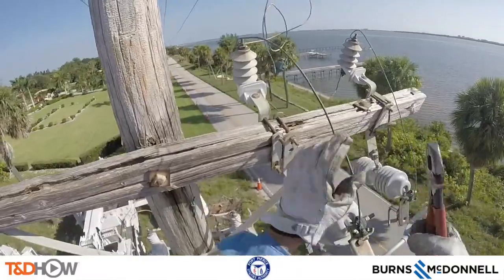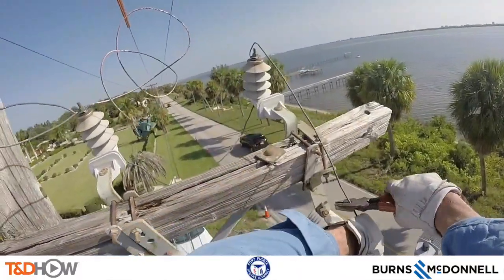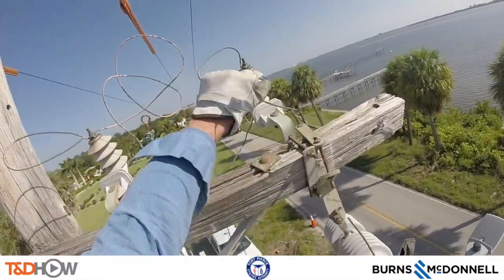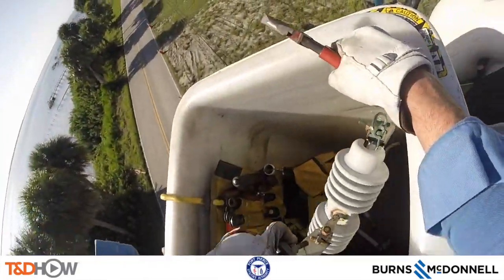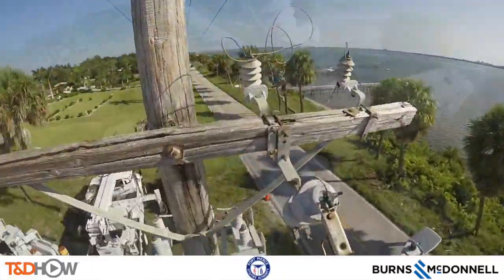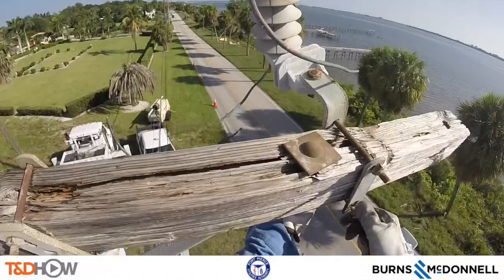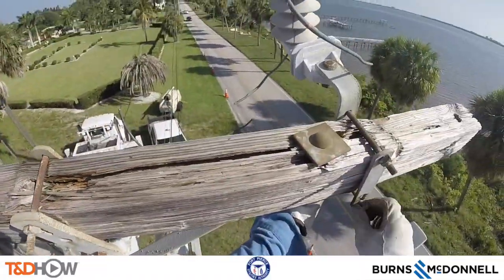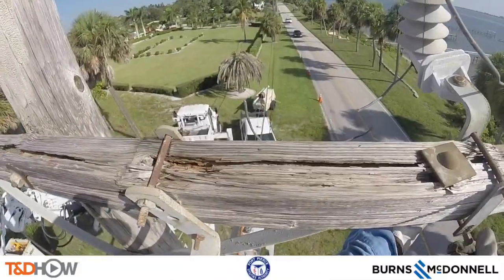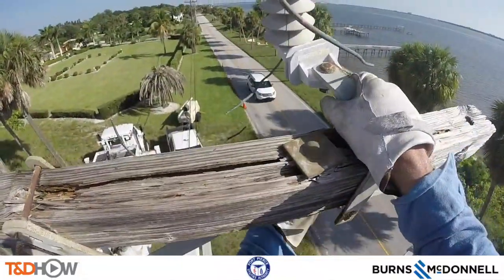As we're watching this, you can see some of the decay of the wood both on the cross arm and on the distribution pole itself as they pull the cross arm away. This work is being done about a week or two before Hurricane Irma slammed into Florida, and it is part of a concrete pole replacement program for deteriorating wood poles such as this.